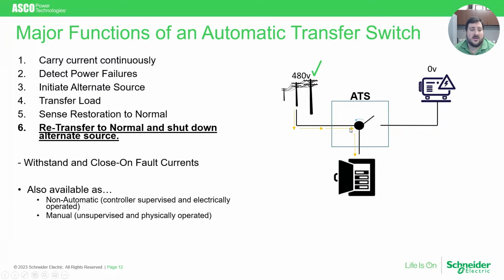It does all that, but at the same time, it needs to also survive any potential faults in the system with withstand and close-on-fault currents. I'll talk about this further in the presentation, but unlike a circuit breaker, the job of a transfer switch is to survive faults in the system and continue to provide power to its load. So it must be able to perform its sequence of operations, which we just reviewed, while also being able to withstand and survive any potential faults in the system while it gets cleared by other pieces of equipment.